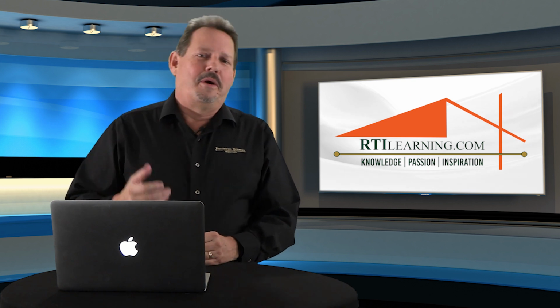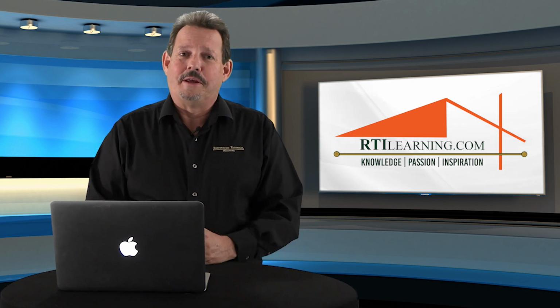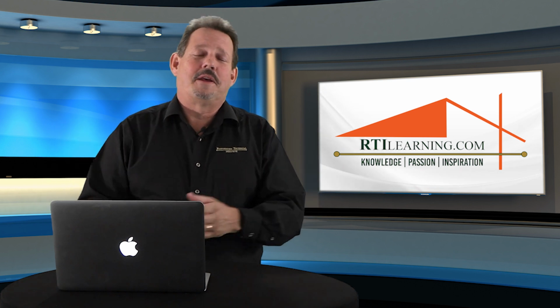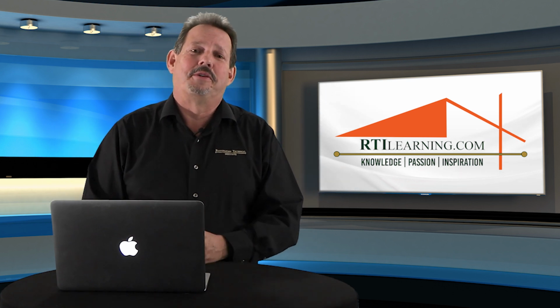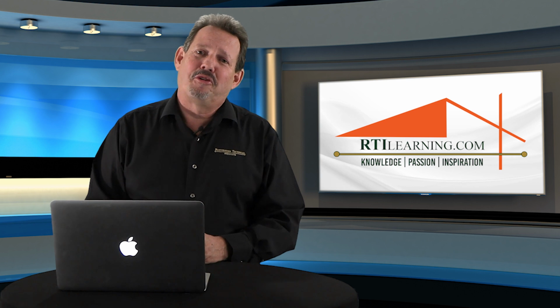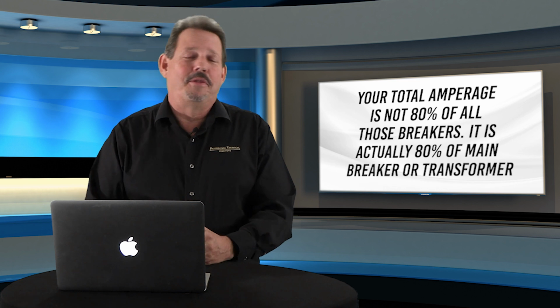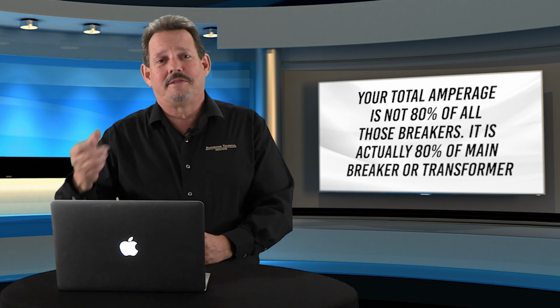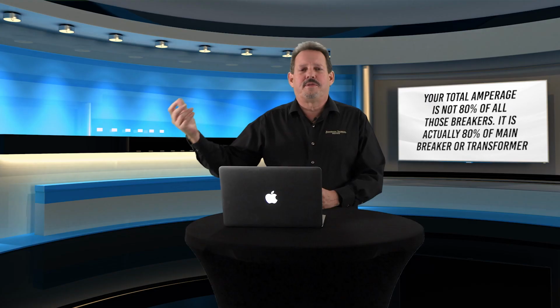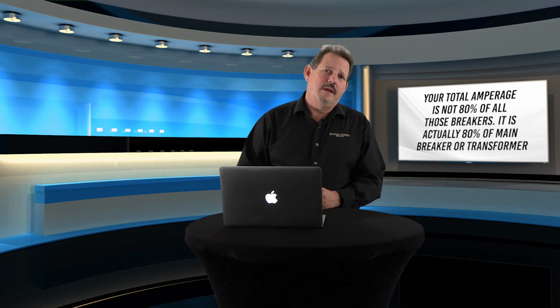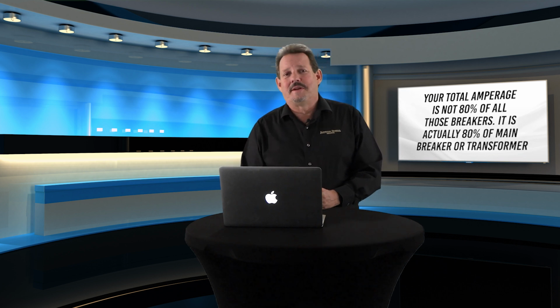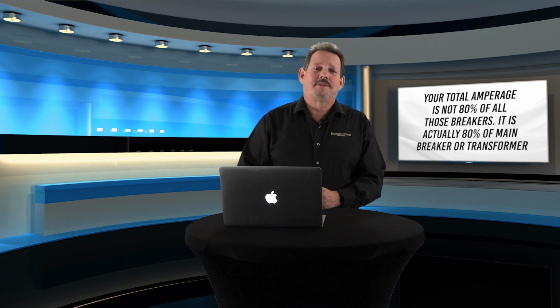Now, you're already upset with me because you can't daisy chain, and I've already taken 20% of the power away from you on the walls, when we never have enough in the first place. It gets worse than that, folks. It all comes back down to the main breaker, or in commercial and residential, it might be the main transformer. If you look in a circuit breaker panel, you'll see maybe 25 or 30 circuit breakers, all at 20 amps. You do not have 80% of that total. You actually only have 80% of the main.